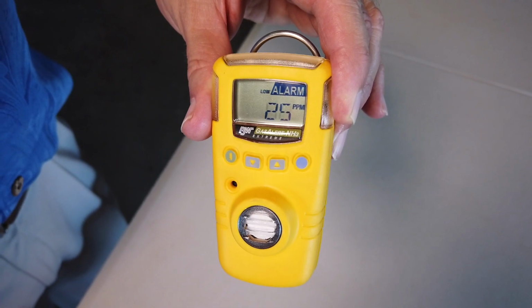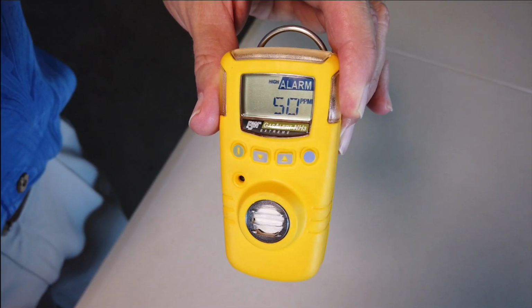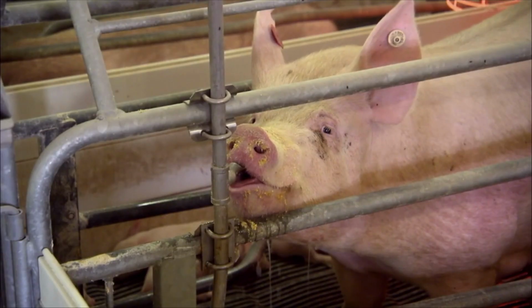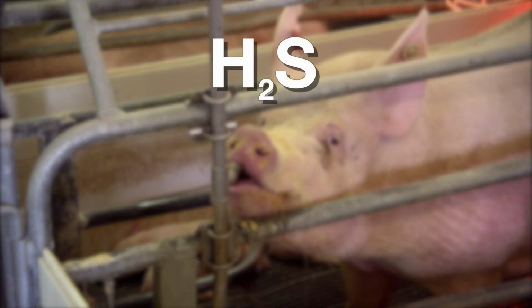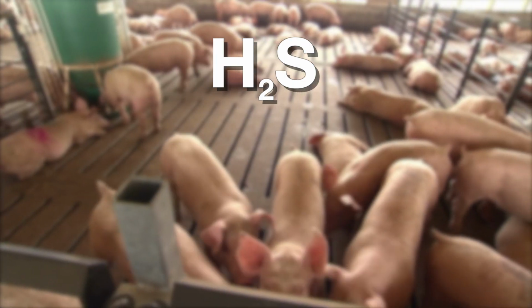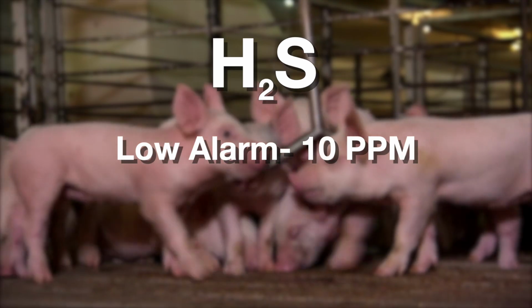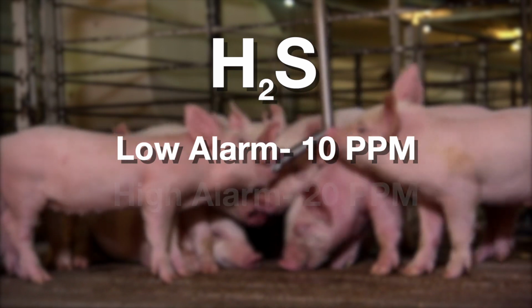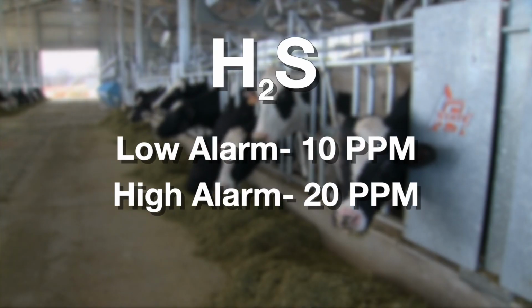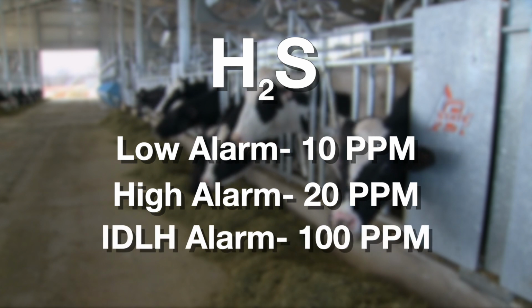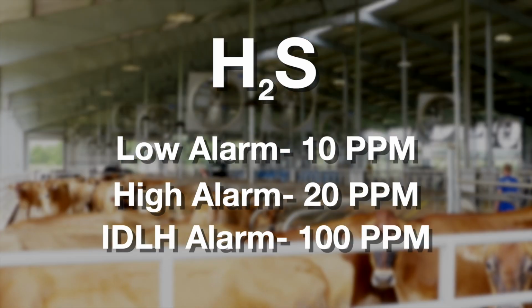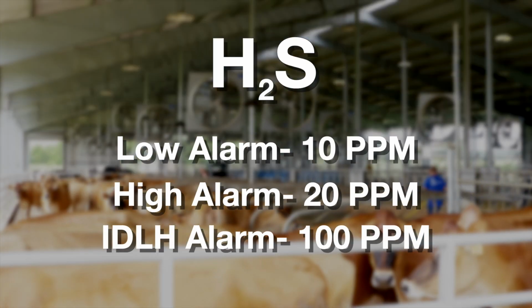Low alarm, high alarm, immediately dangerous to life and health, or IDLH, are all important settings that you need to be aware of. For example, hydrogen sulfide on a gas monitor is typically set at 10 parts per million for a low alarm and 20 parts per million for a high alarm, and the immediately dangerous to life and health, or IDLH alarm, at 100 parts per million.